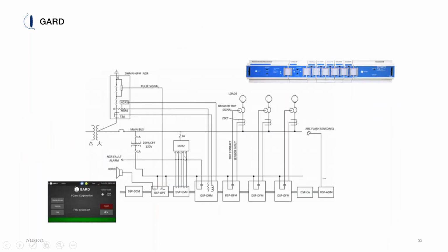We also have the DSP system, which monitors for DC faults on AC systems. You have to keep in mind that just because you have a DC fault on an AC system does not necessarily mean you have a true DC fault. The problem in the past was detecting the means of monitoring DC current through conventional current transformers.